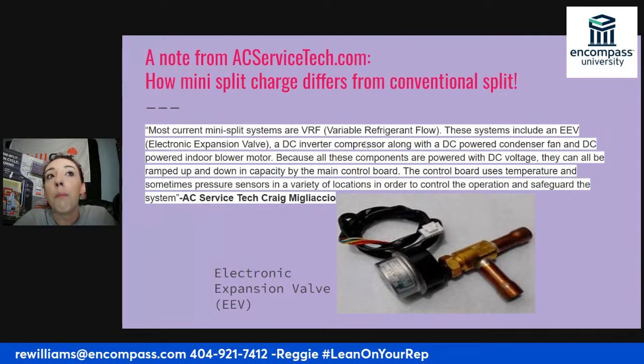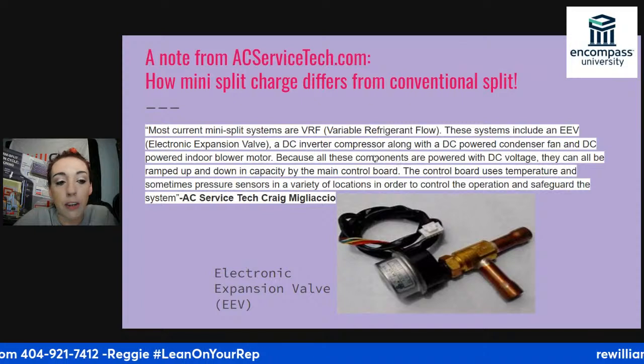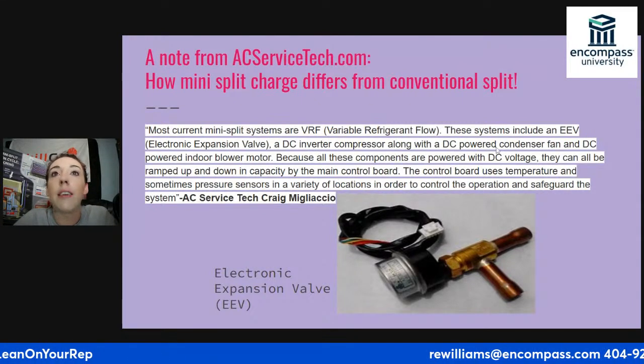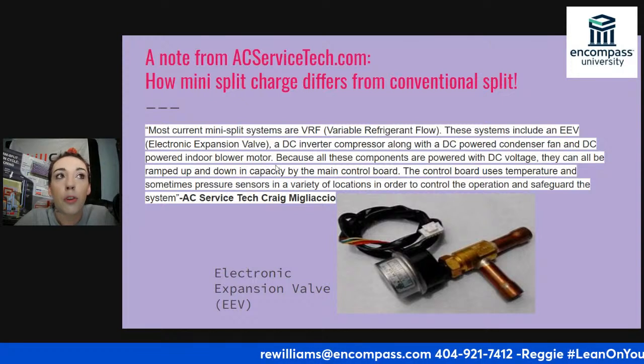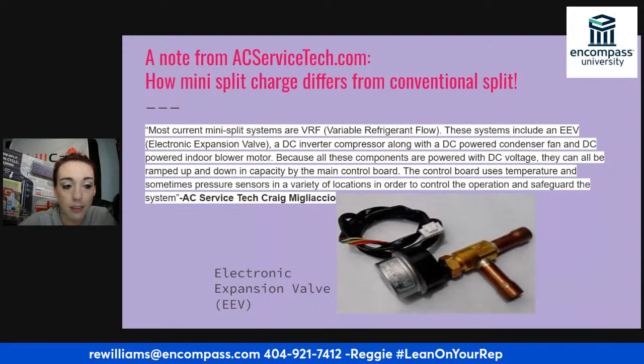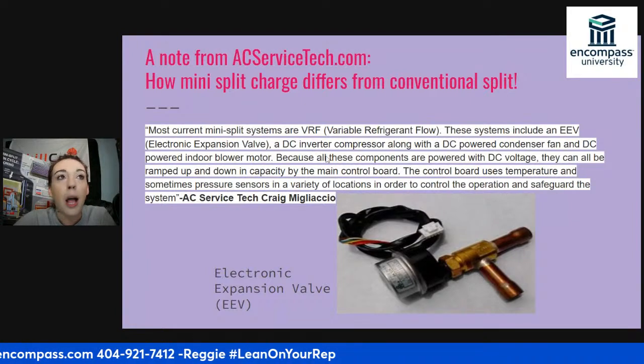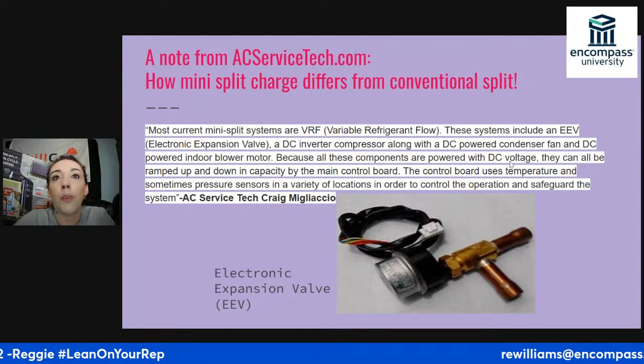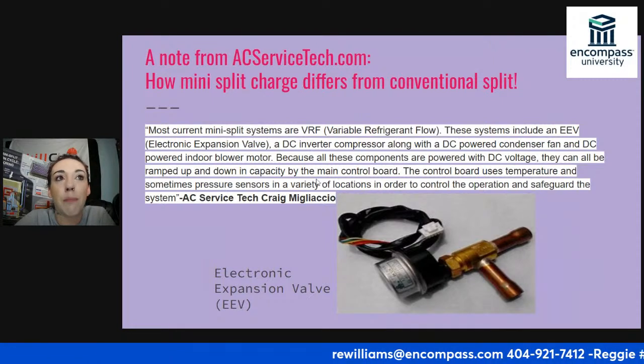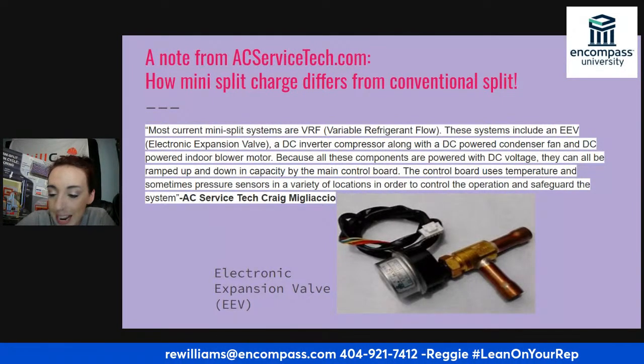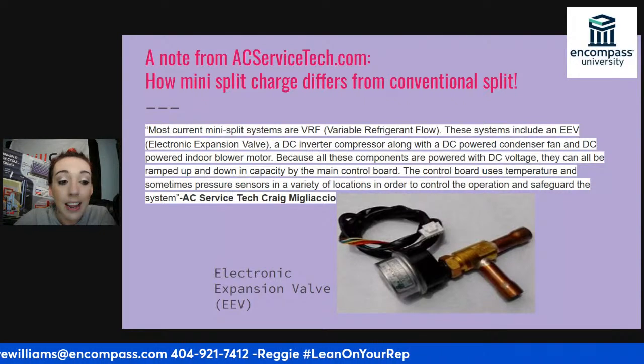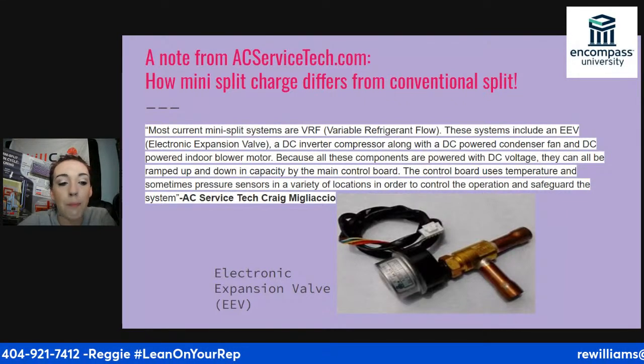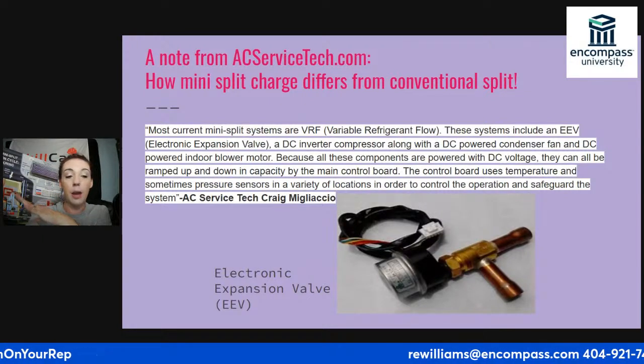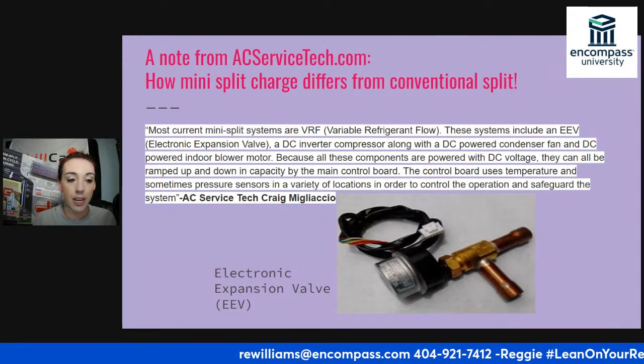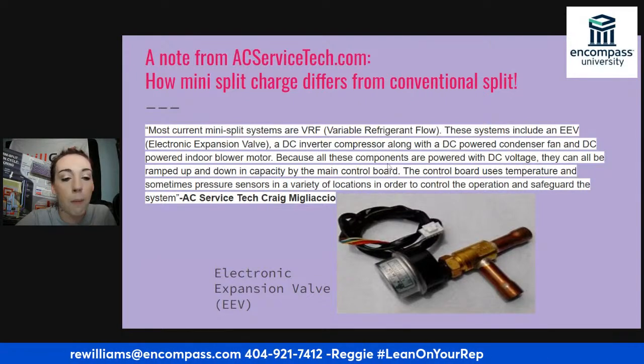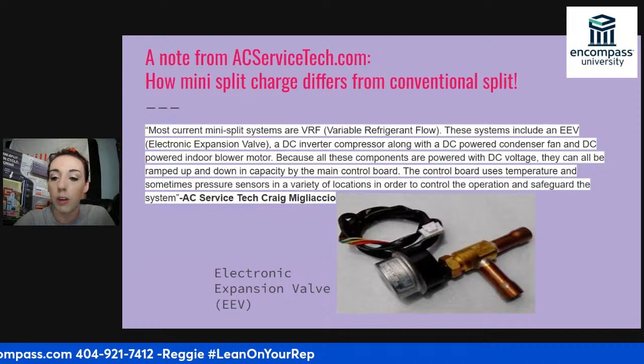A DC inverter compressor. So instead of an AC compressor, we have a DC compressor in mini splits, along with a DC powered condenser fan and DC powered indoor blower motor. So everything in your mini split runs on DC power instead of AC power. Why is that important? Because all of these components are powered with DC voltage, they can all be ramped up and down in capacity by the main control board. So the main difference between a conventional split and a mini split is that variable change. We are able to ramp the fans up when we have a high load, and we're able to drop those fans down when we don't, so that we're not freezing any coils. We have so much more ability for control with a mini split than we do with a conventional split.